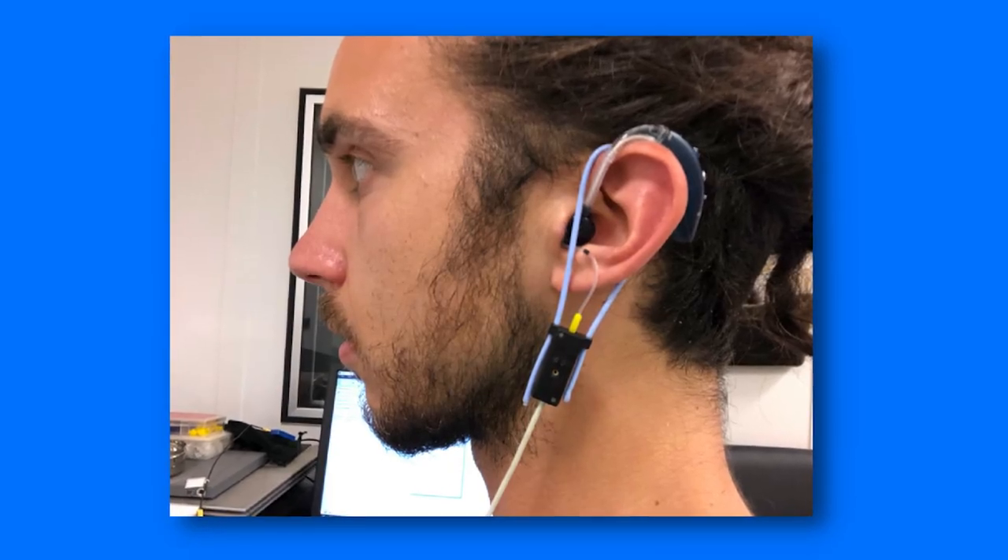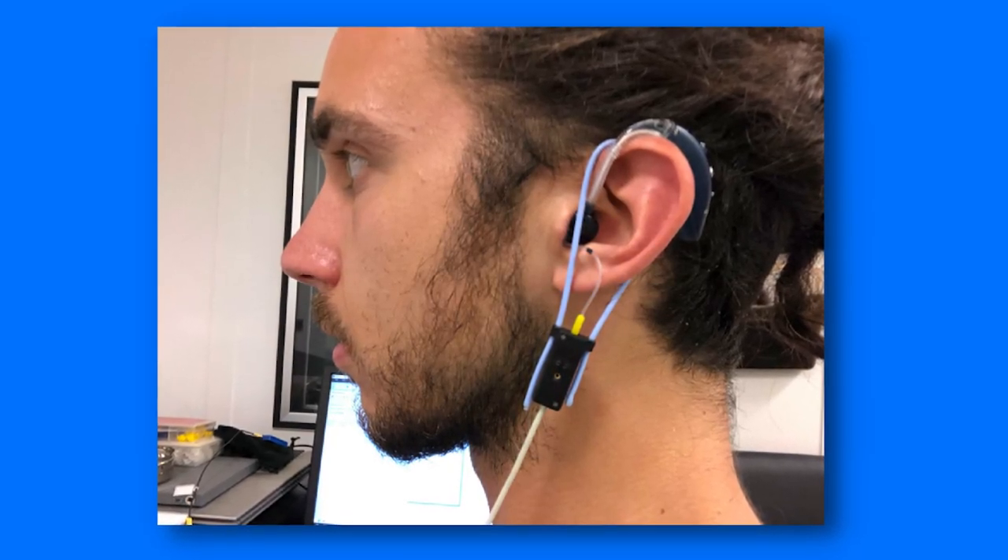I went through the process of putting these on my ears and going to an audiology clinic to run these devices through professional test equipment. Our scientific method is a system called Real Ear Measures, which has calibrated speech signals coming from a speaker, and then I put this hearing aid in my ear and record the output of the hearing aid based on the calibration.